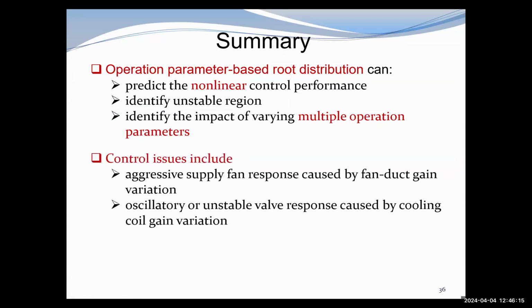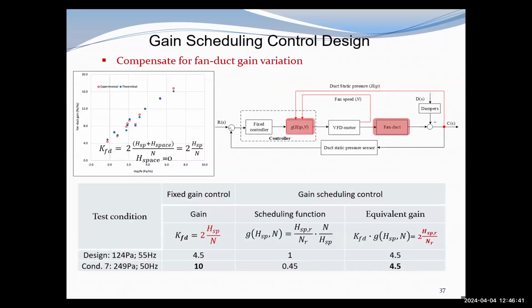And our control issues are that the supply fan speed response will be aggressive, caused by the fan duct gain variation, and the cooling coil valve control system will be oscillatory or unstable, caused by the cooling coil gain variation. To solve these control issues for the fan speed control system, we designed a gain scheduling controller. Inspired by the relationship of the fan duct gain, the duct static pressure and the fan speed, we designed the gain scheduling function correspondingly to compensate for this gain variation. So this is our designed scheduling function.